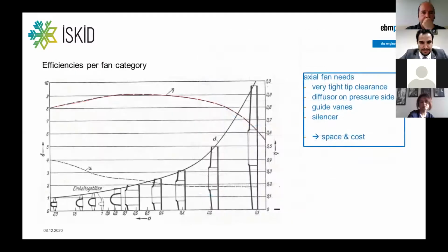But when looking at the theory, which goes back to the Cordier diagram, you see that a backward curved impeller, which is very thin, has a certain pressure development, but the efficiency is low. On the other side, you have a low pressure axial fan with a small ratio between hub and diameter. It's also lower efficiency. This is the efficiency line over the fan families. You see the most efficient fan category is a certain dimension of centrifugal, backward curve. And there's also the possibility to create a very special axial fan that could be on the same level.